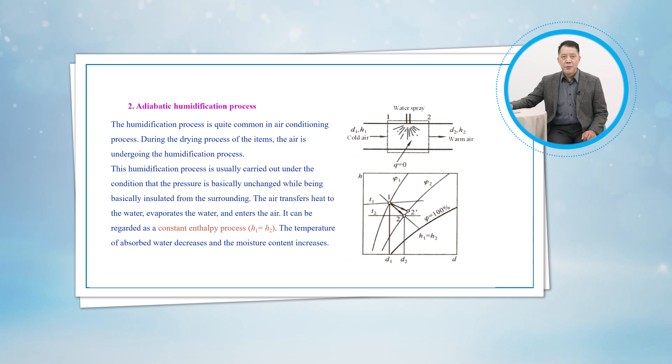If humidification is accomplished by spraying water into the air stream instead, part of the latent heat of vaporization comes from the air, which results in the cooling of the air stream. This process can be regarded as a constant enthalpy process.